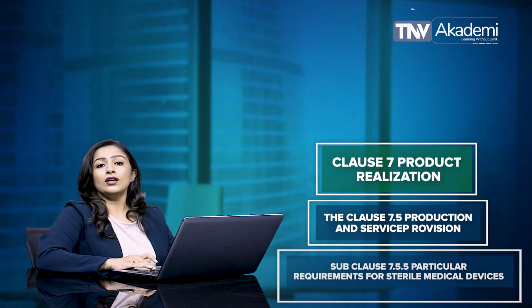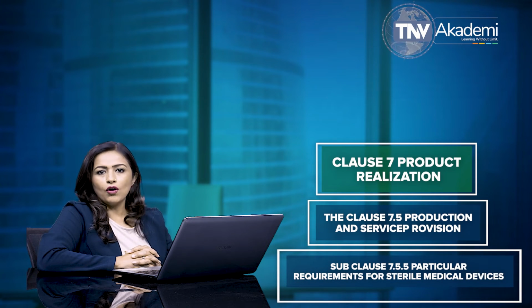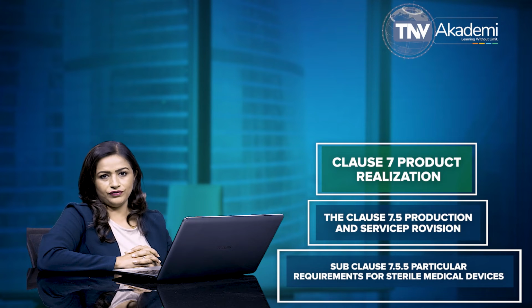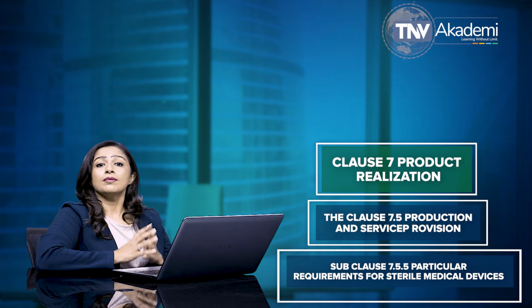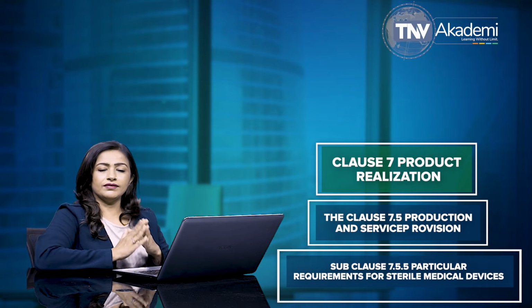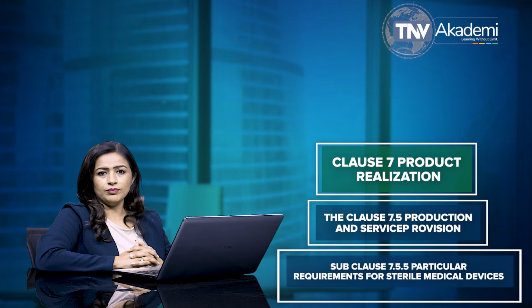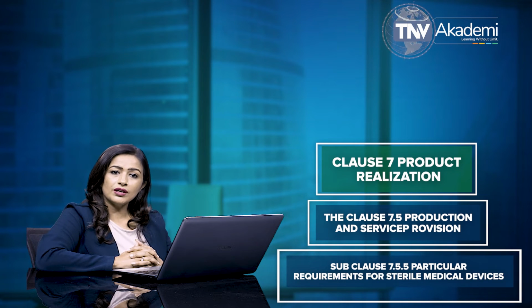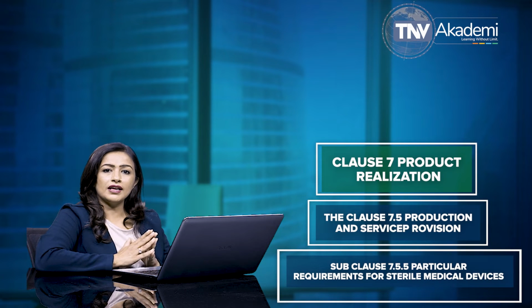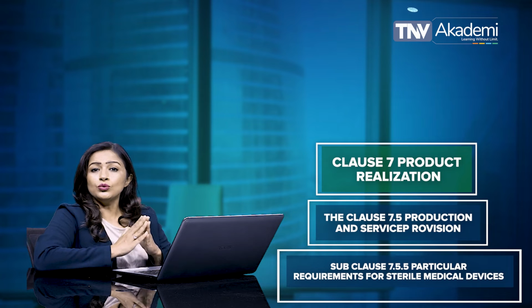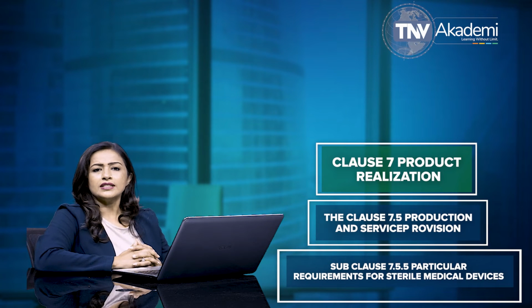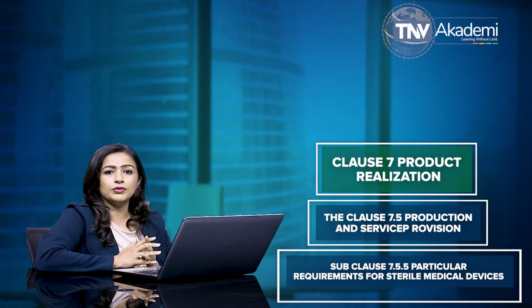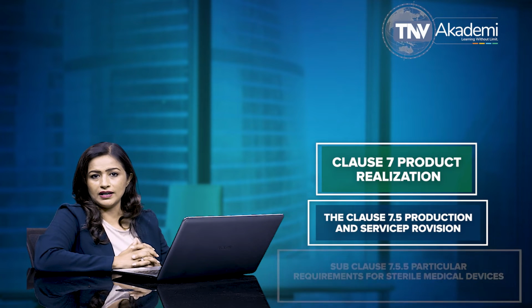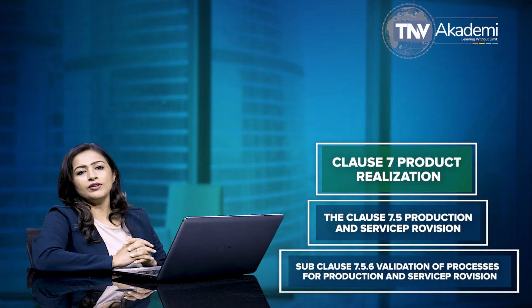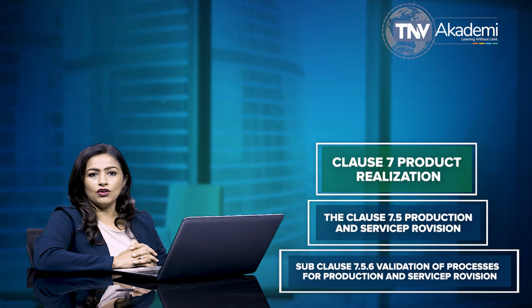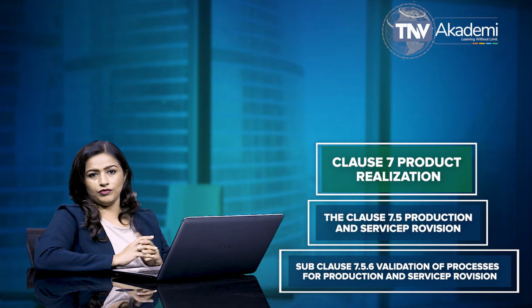Now, let's talk about subclause 7.5.5 of ISO 13485/2016, that is, particular requirements for sterile medical devices. According to this subclause 7.5.5, the organization is required to maintain records of the sterilization process parameters used for each sterilization batch. Sterilization records are required to be traceable to each production batch of medical devices. Coming to subclause 7.5.6, Validation of Processes for Production and Service Provision.